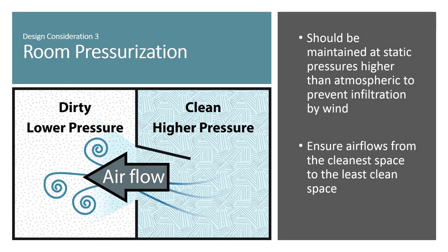Room pressurization. A clean room facility may consist of multiple rooms with different requirements for cleanliness. Rooms in a clean facility should be maintained at static pressures higher than atmospheric to prevent infiltration by wind. Positive differential pressures should be maintained between the rooms to ensure airflows from the cleanest space to the least clean space. The only exception to using a positive differential pressure is when dealing with specific hazardous materials where the statutory health and safety agencies require the room to be at a negative pressure.